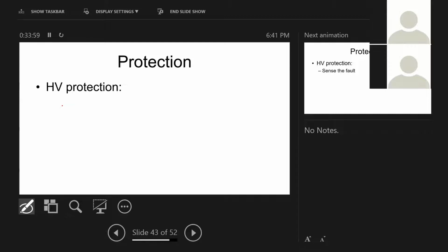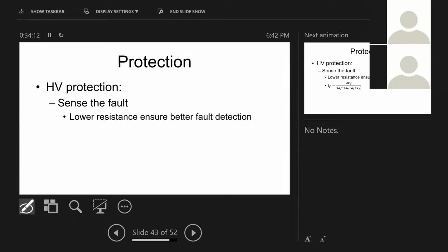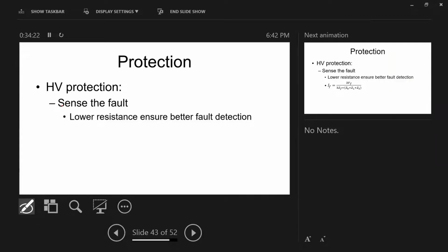Why do I need to sense the fault? To isolate. Now, it's not only to isolate, I have a safety factor. I need to isolate as fast as possible. I needed to sense the fault. To sense the fault, the lower the resistance of your earthing system, the better the sensing mechanism. In reality, I have two types of protection: high fault protection and low fault protection.